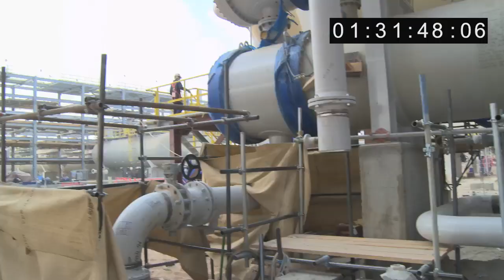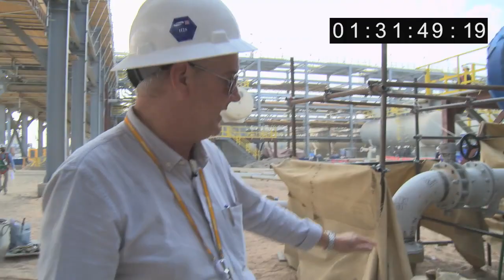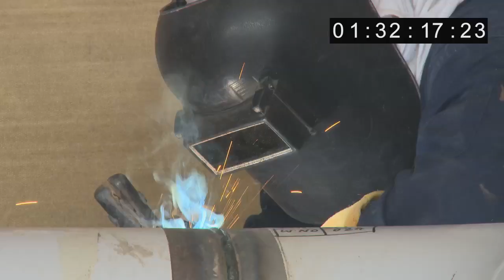Well, at the moment, if you remember, when we last came here we had an elevation problem. This flange here, connecting to the carbon steel flange, didn't match up - basically, the carbon steel piping was far too long. What the guys have done now is reconfigure the pipework insofar as they've cut back on the carbon steel piping to change its elevation to suit the ground piping, which is the GRE cooling water pipe.